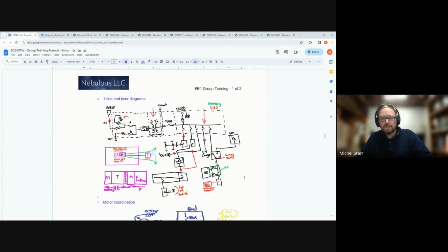So at least, hopefully, the engineers putting it together put the branch panel board on the one line. But especially in drawings of past generations, I've seen that you can also have no panel board shown at all, and they could just have a panel board schedule that shows what the main breakers are and how many branch breakers, and they don't even say which circuits, other than noting number 7 on the floor plan.